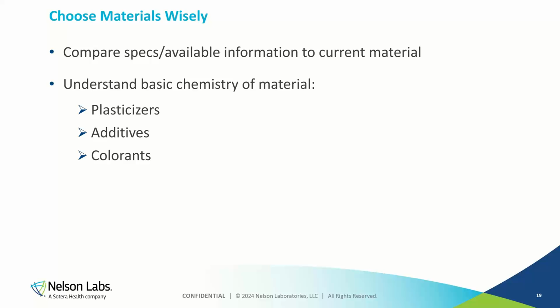So in those cases, when you can compare the specs of the 2 materials and, for the relevant endpoints that you have, they are matching or there's available information, I think then your change is much simpler and may not even require additional extensive testing. Maybe you should still run a cytotoxicity test and look at some other specific things that might be really important for your specific device, but there is a chance to use a scientific rationale to show that you are changing like to like. Obviously, you need to still have a risk assessment written. But the point is that you need to understand the basic chemistry of your material.